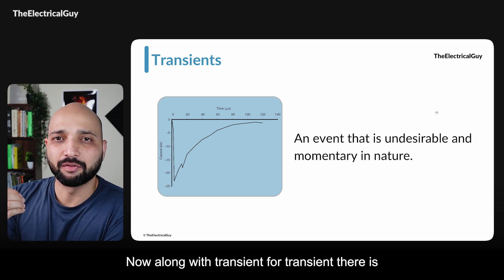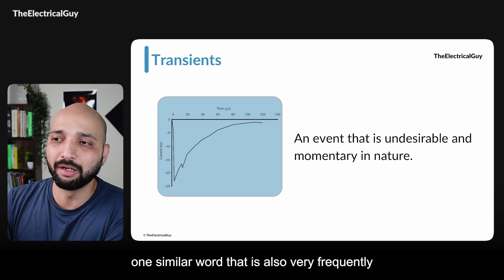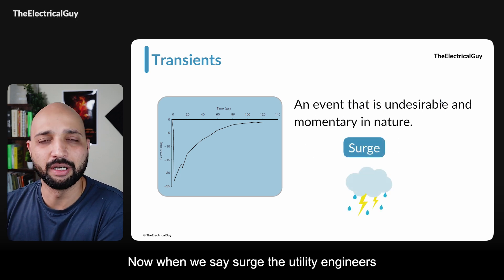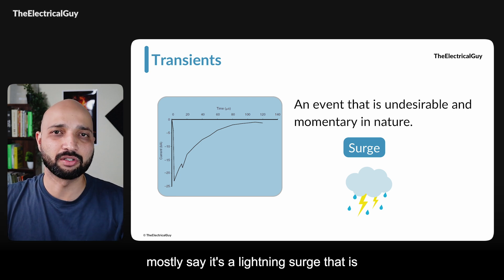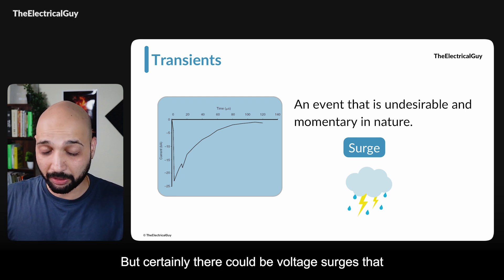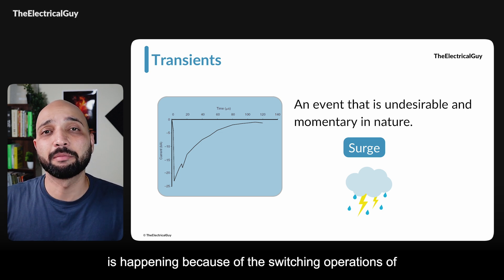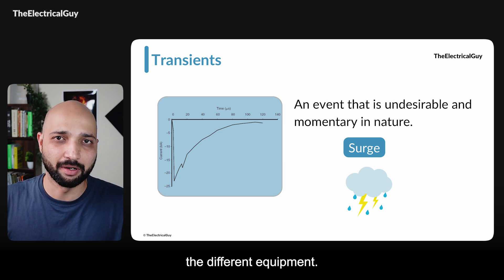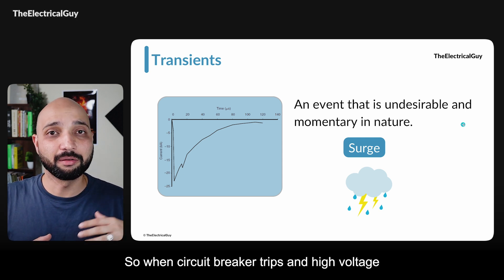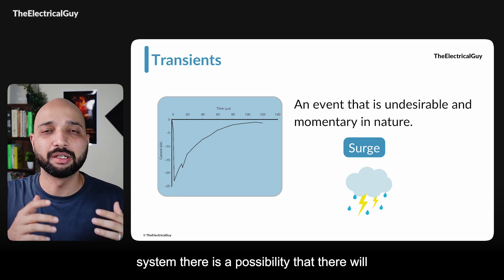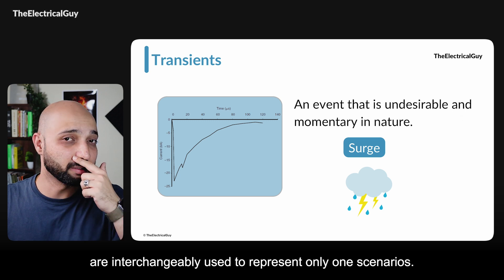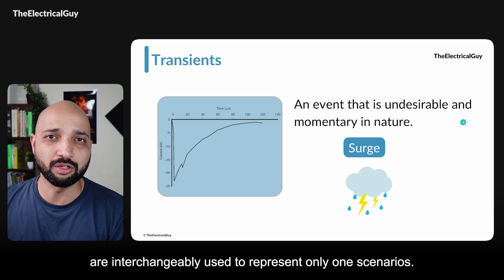Along with transient, one similar word frequently used is surge. Utility engineers mostly refer to lightning surges happening in the system, and to protect against that we need lightning arrestors. But there could also be voltage surges because of switching operations of different equipment, which is seen in high and extra high voltage systems. When a circuit breaker trips in a high voltage system, there is a possibility of a switching surge. Surge and transient are words interchangeably used to represent the same scenario.